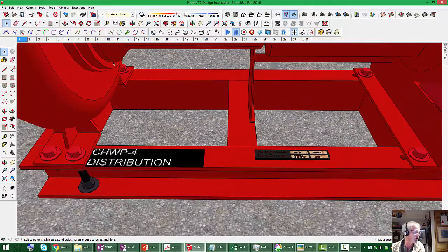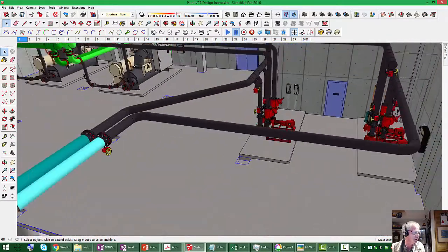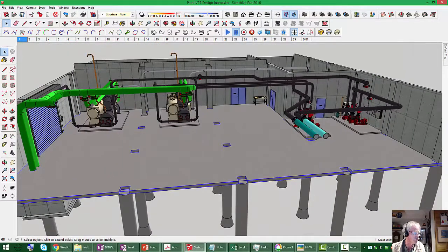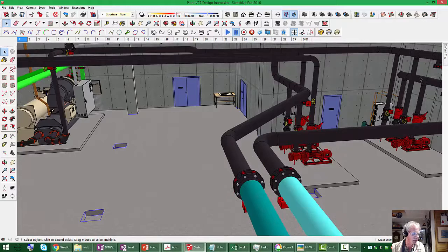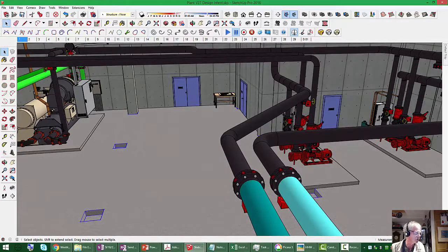If it only has 1100 GPM capacity, there's a pretty good chance that the plant isn't intended to have both machines running simultaneously. If it has 2200 GPM of capacity or so, probably means the plant was designed for both chillers to run concurrently. And if it has even more capacity than that, it probably means the plant is actually intended to have additional capacity added to it at some point. Another clue in that regard would be if you go back here and look at the piping a little closer, you discover there's some capped T's in the piping, both here and where the chillers are. That kind of implies they have provisions there to add pumps and add chillers.